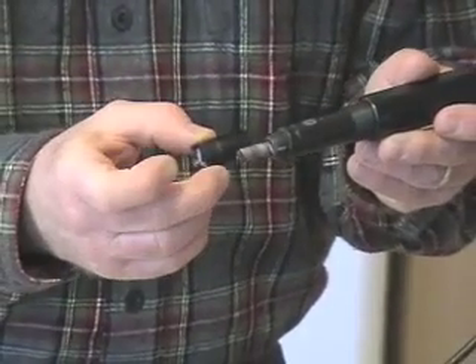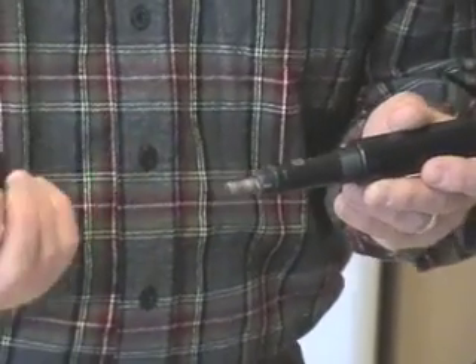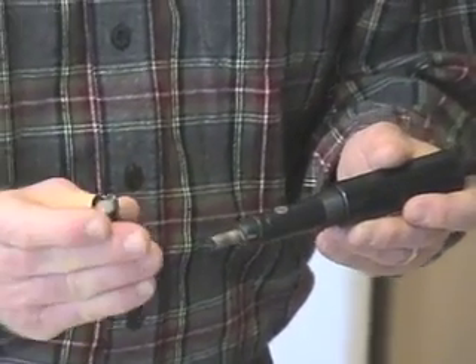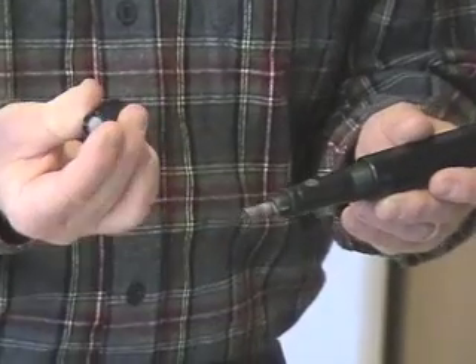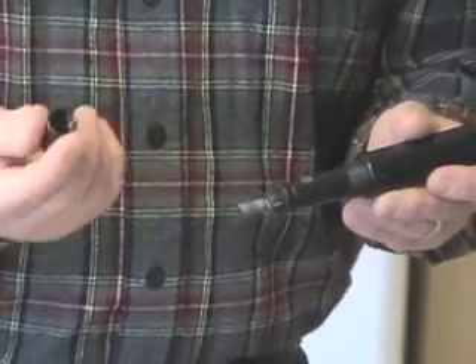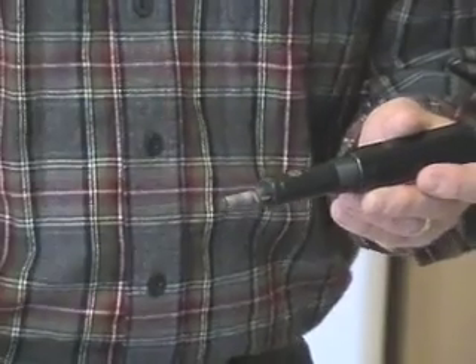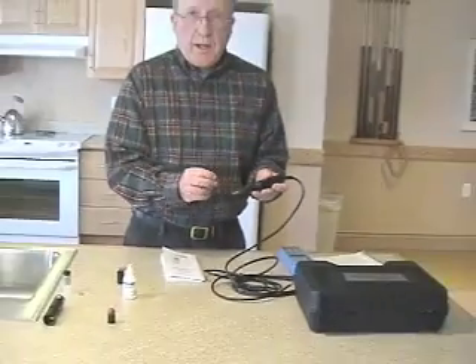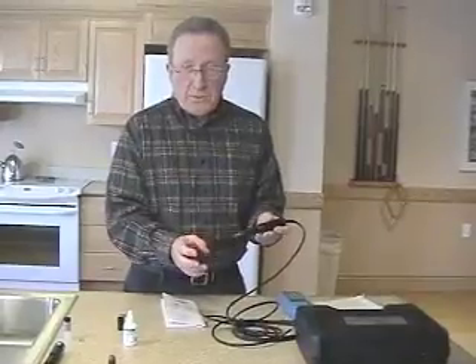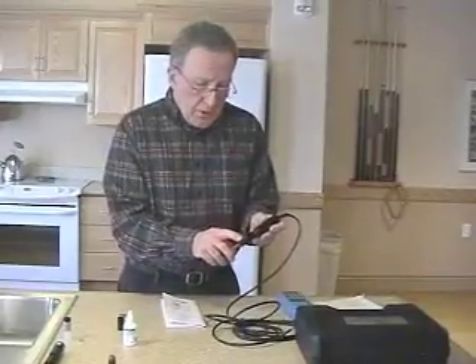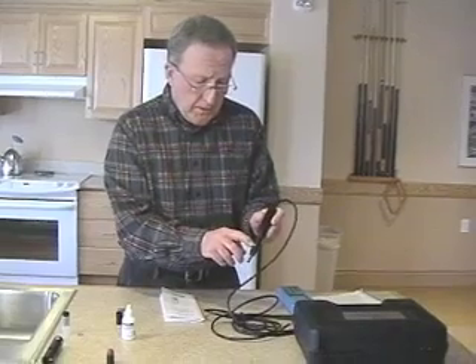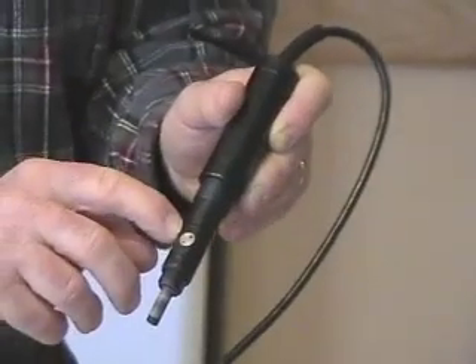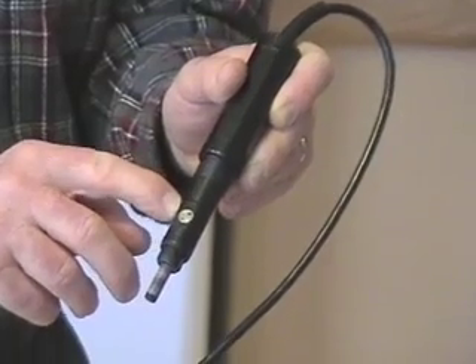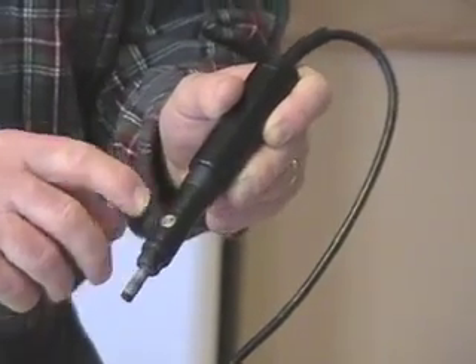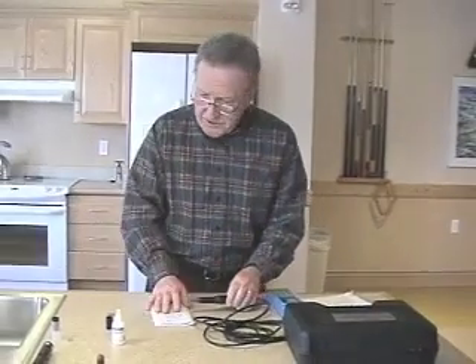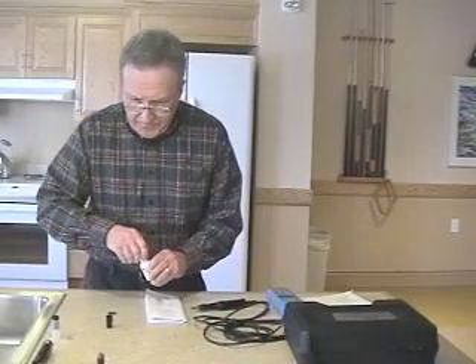There's a membrane cap that fits over top of the sensor. This cap will have electrolyte inside. There's a semi-permeable membrane at the end of the cap. That membrane allows the transfer of oxygen atoms from the water through the cap to attach to the cathode, and that's where your measurement occurs. Here there's also a circular thermistor, and this is used to record your water temperatures.